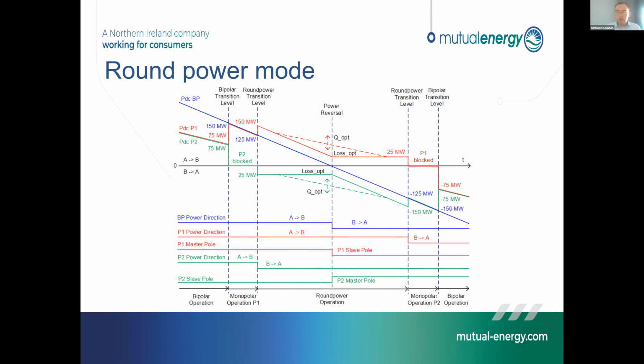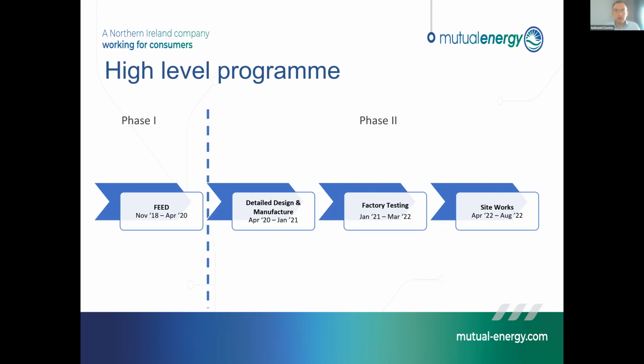This is just a diagram. The numbers aren't exact, they can be altered, but basically there are transitions from that round power operation through to monopolar, and then bipole where both poles are operating, and that's all to do with optimizing losses and reactive power. There are these transition points that we can change and play around with depending on what the optimal scenario is. Okay, if you can flick on to the next point, Sam.